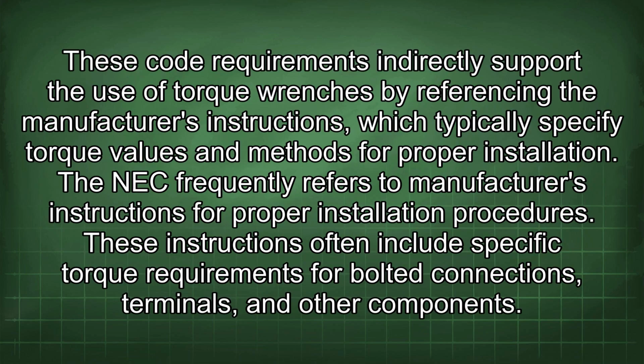These code requirements indirectly support the use of torque wrenches by referencing the manufacturer's instructions, which typically specify torque values and methods for proper installation. The NEC frequently refers to manufacturers' instructions for proper installation procedures. These instructions often include specific torque requirements for bolted connections, terminals, and other components.